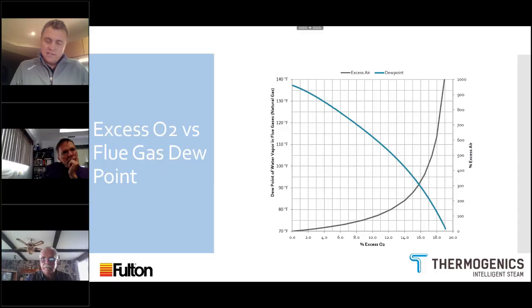The only other thing too, JJ, is steam traps sometimes will operate inaccurately depending on the pressure differential across them. So I know Enbridge has a strong incentive for that. There's a lot of people here that have to deal with maintenance, and that really is our time and money. So if you want to implement something like a pressure reduction, look at it from a maintenance perspective first and understand the impacts from some of your vendors. Talk to the trap survey guy, talk to your steam specialties group in terms of what impacts that turn down might have on the wear and tear of your system. That's the unspoken downside that we're seeing every day.